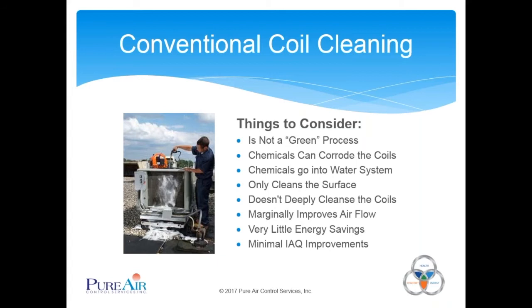Yeah, that's absolutely right, Frank. I think that as this water pushes into the coil where it's fouled, it's going to just hang out there, so it's going to look clean. It'll smell a little bit cleaner, but then you're still not getting really good airflow through the coil. And so basically that's what equates to very little energy savings. If you're not getting the fouling out of the core of the fins and the core of the coil and improving that airflow and that efficiency, that's where your energy efficiency is going to come from.